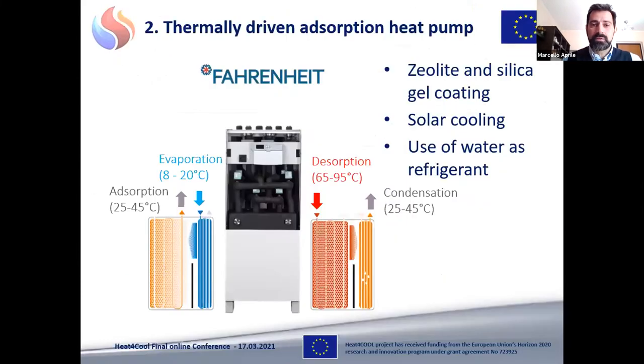Next, moving to the heating and cooling technologies that have been developed and demonstrated, I will briefly present the main innovations supported by the project concerning heat pumps. Fahrenheit developed a new adsorption chiller using zeolite coated heat exchangers, in addition to the one based on silica gel heat exchangers. Such units are suitable for solar cooling since they can be operated with low desorption temperatures. In the case of silica gel, the minimum driving temperature is approximately 60 degrees Celsius.